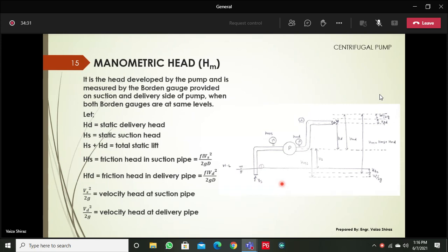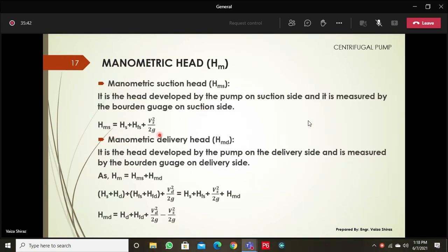Next is the manometric head — the head developed by the pump, measured by gauges on the suction and delivery sides. H_s is the static suction head, H_d is the static delivery head, and their sum gives the total static head. H_FS is the friction head loss in the suction pipe, H_FD is the friction head loss in the delivery pipe, both derived from Darcy's equation: V²/2g times the respective pipe parameters. H_MD is the manometric head on the delivery side. These equations are important for pump design.